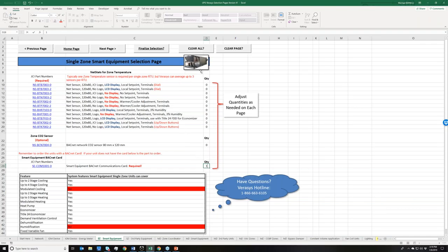When doing so, the biggest thing with smart equipment is we cannot use a standard thermostat with Verasys. We wouldn't want to, because a smart equipment board houses a lot of the brains inside of it, and a thermostat connected to it will override those features. So we really want to use a NetStat off the smart equipment rooftop unit to monitor space temperature.